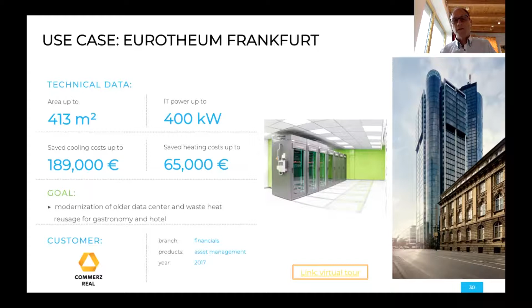There's also an efficiency value you can calculate, how this looks before the renovation and after. Before the renovation, we had a PUE of 1.92, meaning a lot of energy was wasted. The new PUE is 1.27. That means for every kilowatt that goes to the servers, another 270 watts is needed for the infrastructure around it. Most of these 270 watts needed for the infrastructure is not going to the cooling, because that's a very small amount now. A lot of it is also going to uninterruptible power supply and these kind of things.